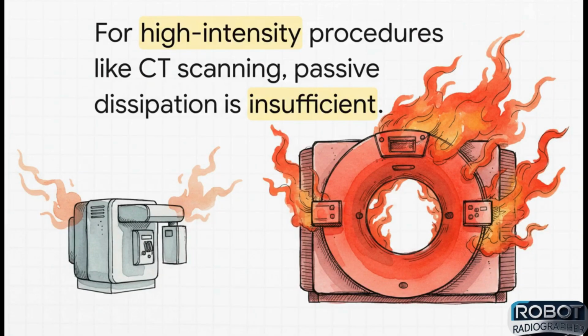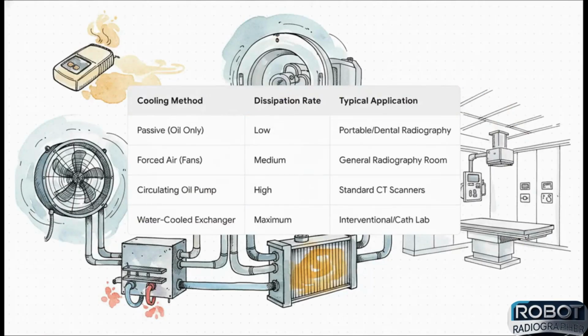For a simple dental X-ray that's used every now and then, just letting the heat passively radiate off the housing into the air is fine. It works. But for machines that are used over and over again, like CT scanners, no way. That's way too slow. The machine would overheat in no time. These powerful systems need active cooling. And this chart really shows you the ladder of cooling power. You can see the clear progression, right? You've got simple passive cooling for small, portable units. Then you add fans for a standard hospital radiography room. For the really powerful CT scanners, they actually use pumps to circulate the oil through an external radiator, kind of like in your car's engine.